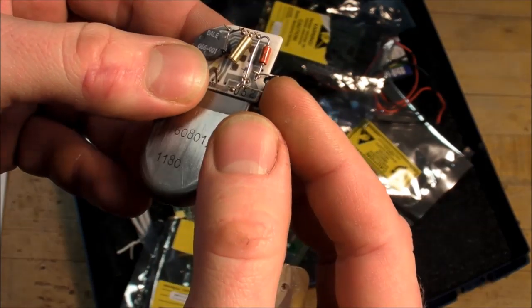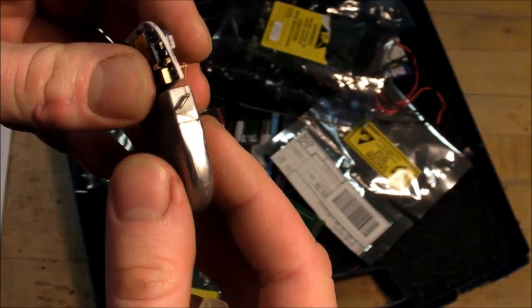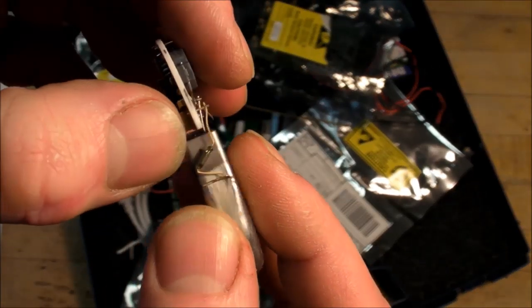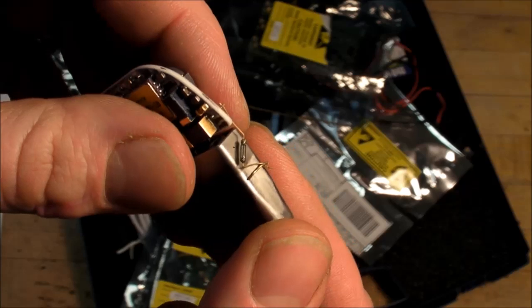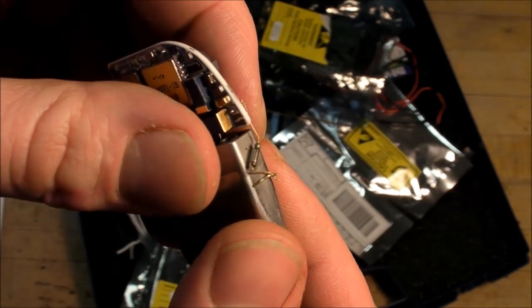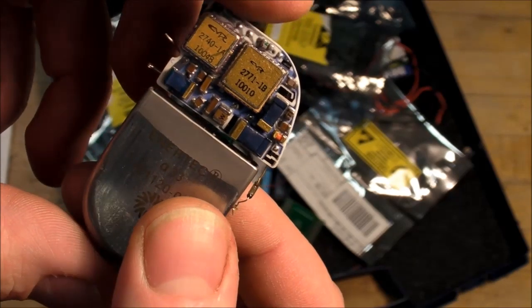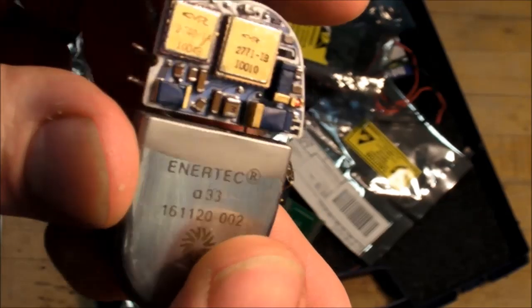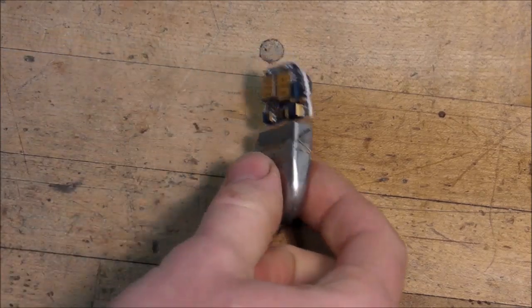The students already cut some wires here. This one just went to the battery, this one is ground, this one is the output to the outside of the case. What's really interesting here is that there is a very tiny reed switch. So apparently the doctor or the patient, somebody would hold a magnet or an electromagnet up to the chest and close the circuit in that reed switch. Don't know what it would do, maybe if you give it a magnetic pulse in a certain sequence then it'll either increase or decrease the rate at which it sends a pulse to the heart.